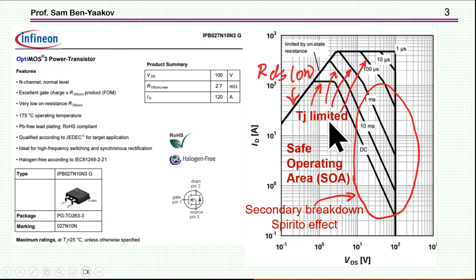You have to be below it. And for example, if the voltage is 10 volt on the transistor and we have a 1 millisecond curve, the current shouldn't be higher than, say 150 amp. So this is a limitation in the linear mode.